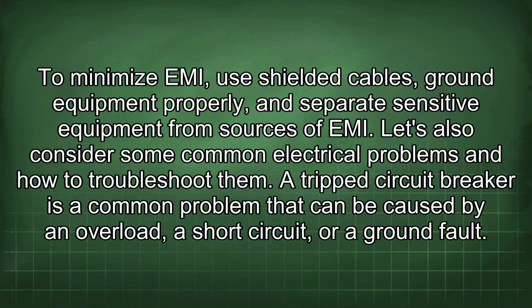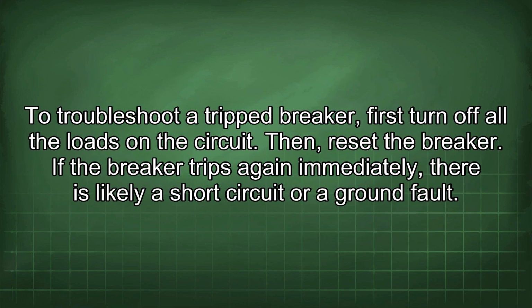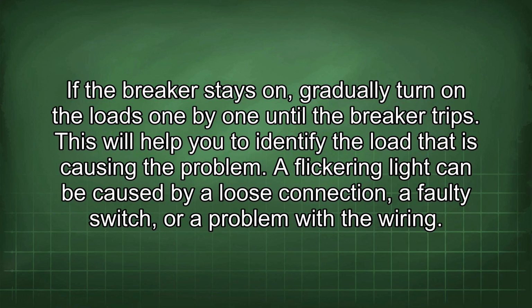Let's also consider some common electrical problems and how to troubleshoot them. A tripped circuit breaker is a common problem that can be caused by an overload, a short circuit, or a ground fault. To troubleshoot a tripped breaker, first turn off all the loads in the circuit. Then reset the breaker. If the breaker trips again immediately, there is likely a short circuit or a ground fault. If the breaker stays on, gradually turn on the loads one by one until the breaker trips. This will help you to identify the load that is causing the problem.